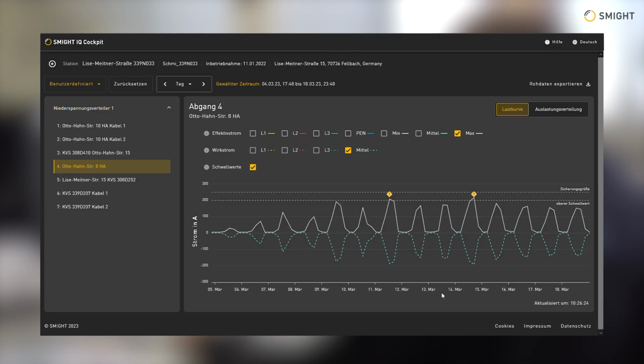And whether there is an overload on the equipment. Not in this case. If the customer were to install more solar panel modules now, we would have to react, because we can see in the SMIGHT IQ Cockpit here that we don't have much headroom left up to the fuse rating.